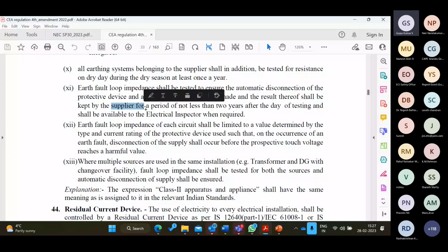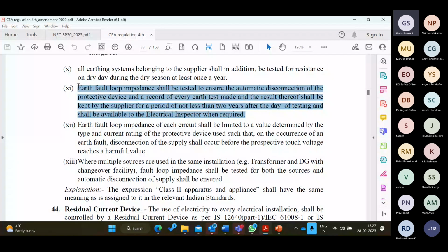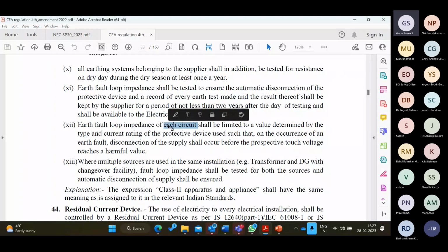Unfortunately, we don't have the habit of testing fault loop impedance. Fault loop impedance has not only become mandatory, it has become a responsibility of the electricity supply company. They are supposed to do the testing if there is a public electricity distribution, and they are supposed to keep it in their records for not less than 2 years. The next one, earth fault loop impedance of each circuit. Each circuit belongs to the owner of the building.